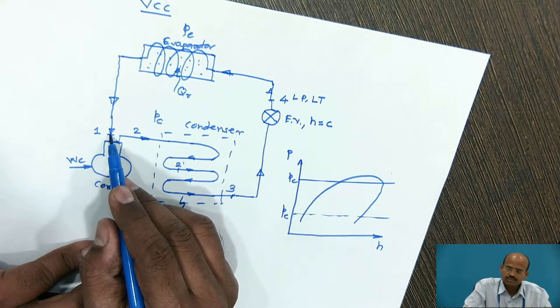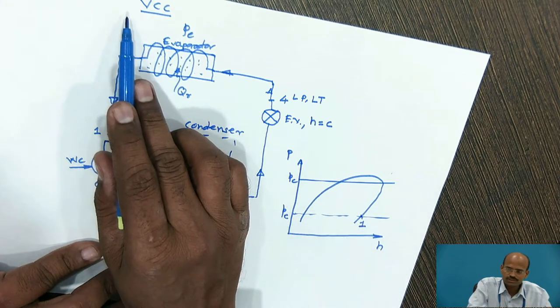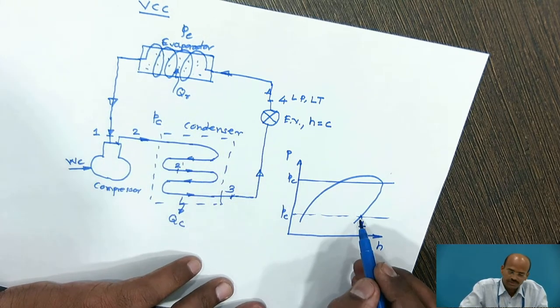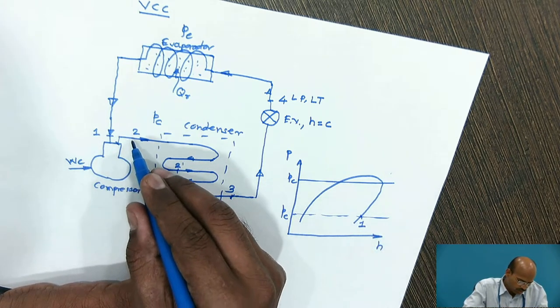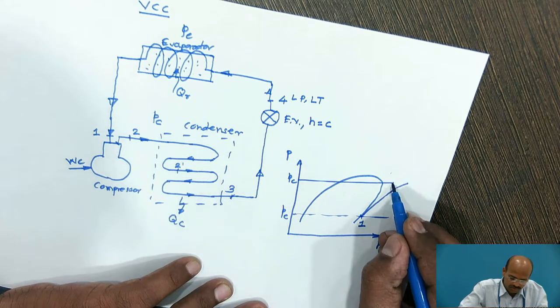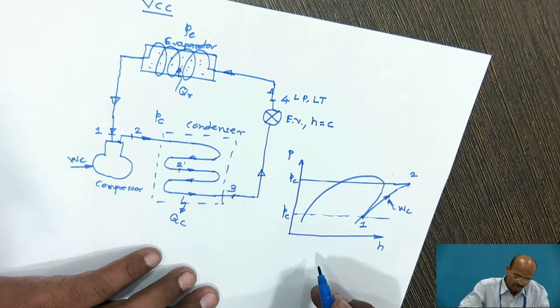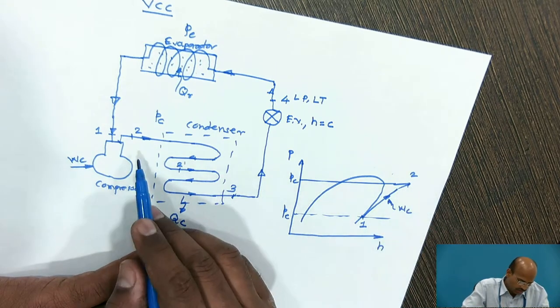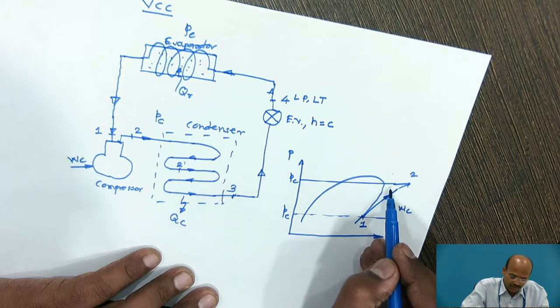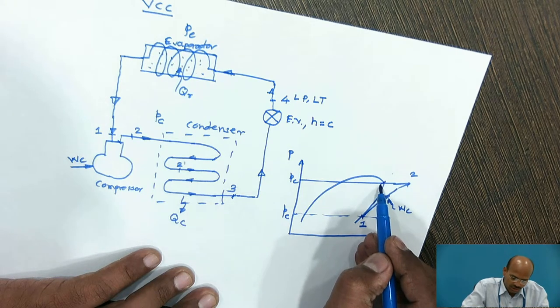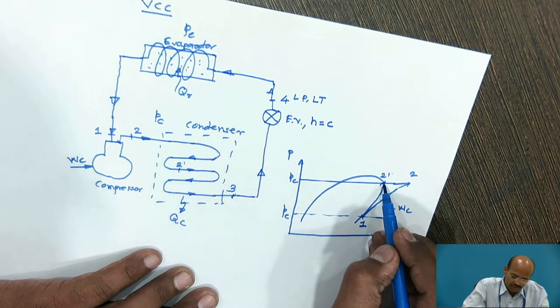Point 1 is the state of the refrigerant at inlet to the compressor — dry and saturated. For theoretical VCC, we assume the state of the refrigerant at the outlet of the evaporator, or inlet to the compressor, is dry and saturated. Process 1 to 2 is the isentropic compression process. The superheated vapor refrigerant then enters the condenser, where due to its high temperature it starts desuperheating by rejecting heat to the surrounding — from point 2 to 2-dash. So 2 to 2-dash is the desuperheating process.